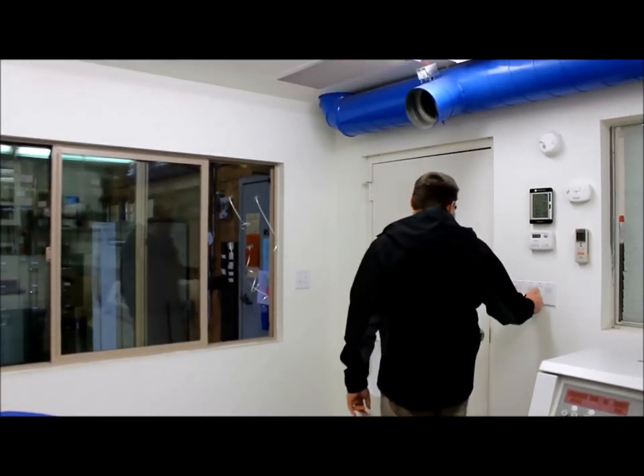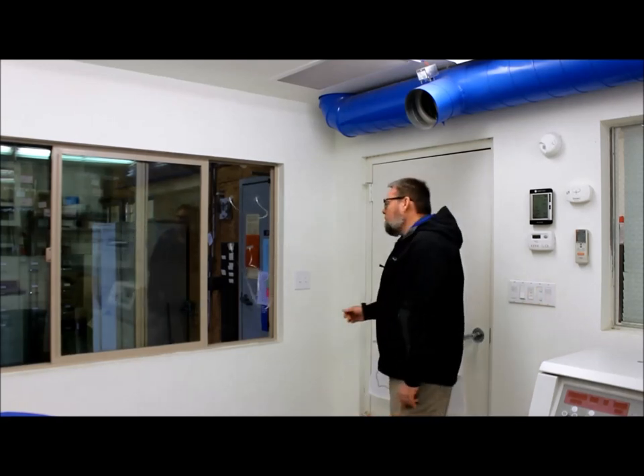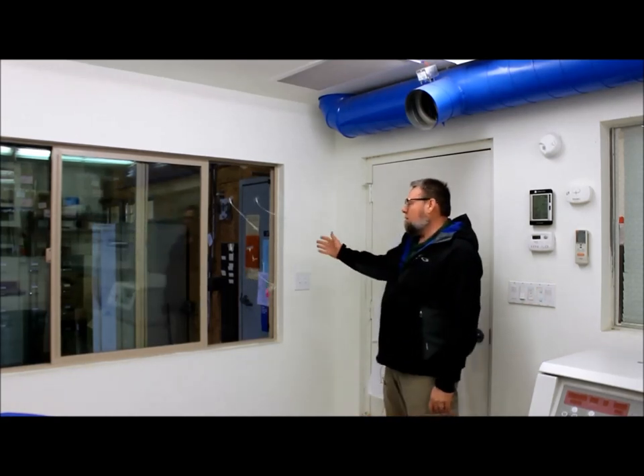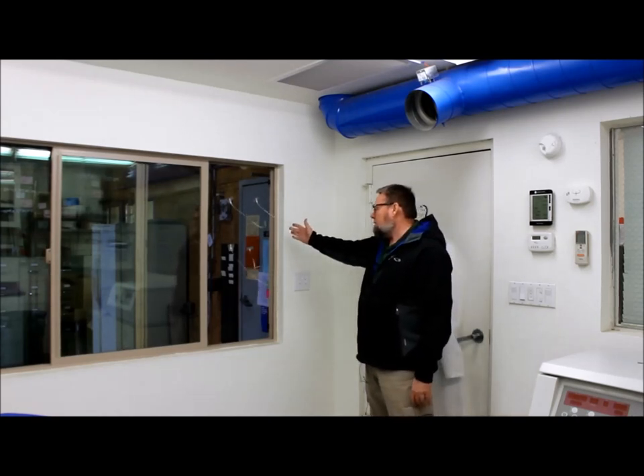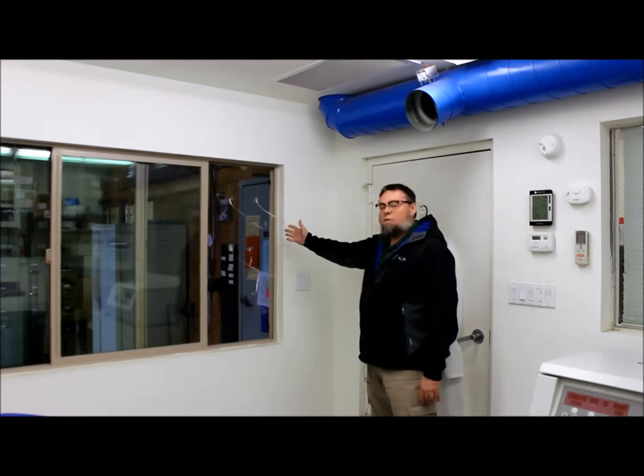I'll go ahead and kick it into high speed. The noise level picks up slightly, but we double the airflow. Now we're at 4200 cubic feet of air a minute and you see the streamers are moving quite nicely. They're not straight out, but they are doing well.